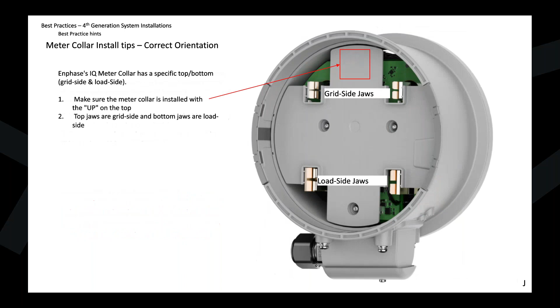So again, let me go back one here. Meter collar, again, up here: grid side, load side, wiring in an external meter pan. Again, make sure you bring your utility, your grid side, at the top, load side at the bottom. Following those two is going to ensure polarity and phasing is going to be correct throughout the system.